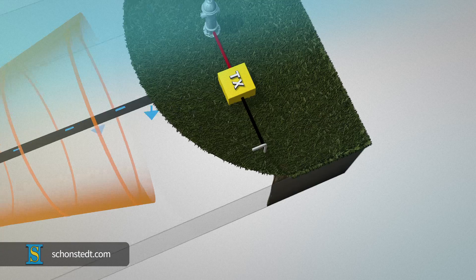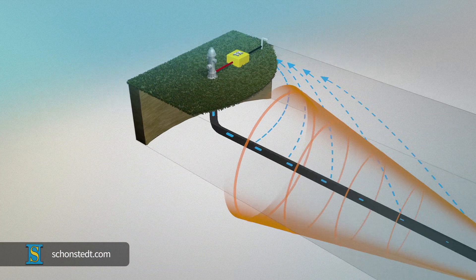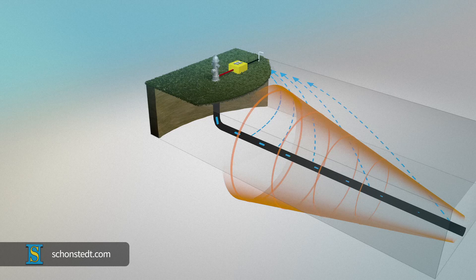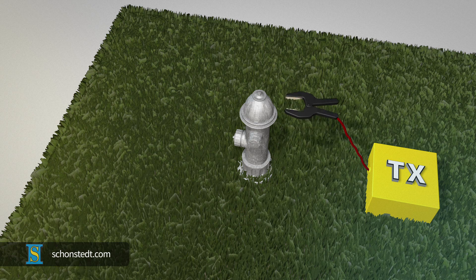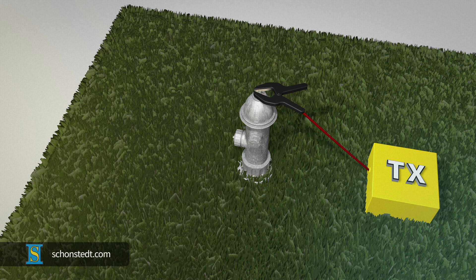With the direct method, you must make a direct connection to the pipe or cable being located. This concentrates the signal on the targeted line. First, take the clip attached to the red cable and apply it directly to the pipe or cable you're trying to locate. Make sure there is a good metal-to-metal contact.